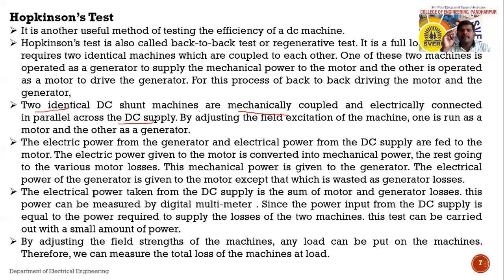Some EMF can be induced by a generator. This induced EMF, or the output power generated by the generator, is fed as an input to the motor. So we are feeding the generator output as an input to the motor. That means we are conducting a back-to-back test, or we can call it a Hopkinson test. While conducting this test, these two identical machines are mechanically coupled.